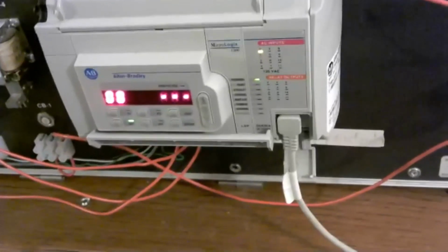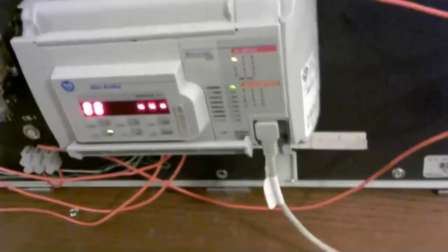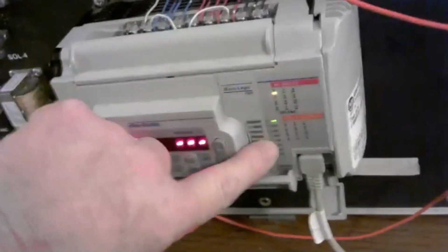You can take that end cap terminator off and slide that off like that. And you can actually add some more modules on there like we did up here. So you can make this same PLC modular. Right now it's called fixed I/O, or fixed input output, because you can't change them.